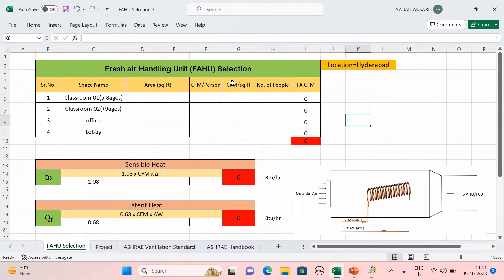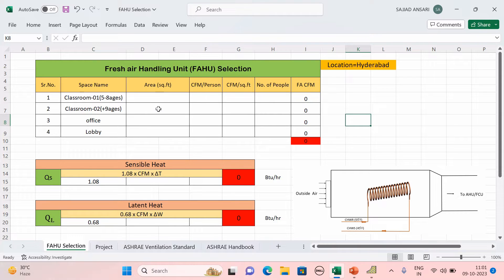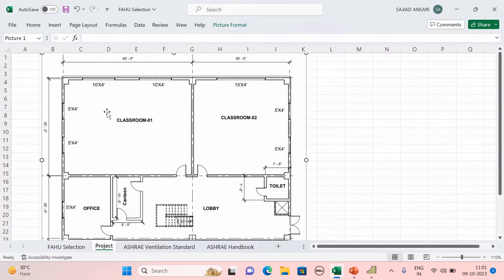To find out the fresh air CFM, we have a formula: CFM per person × number of people + CFM per square feet × area. That is why first we need to calculate the area of each and every space. You get the area from the layout — just open your project.